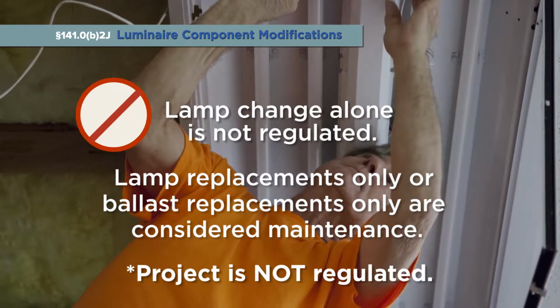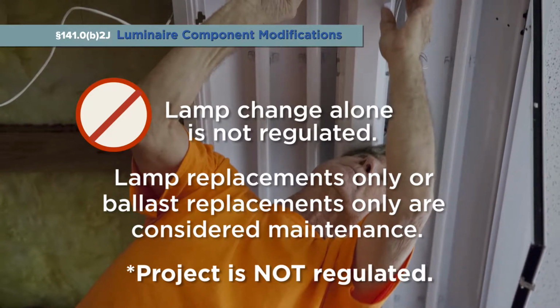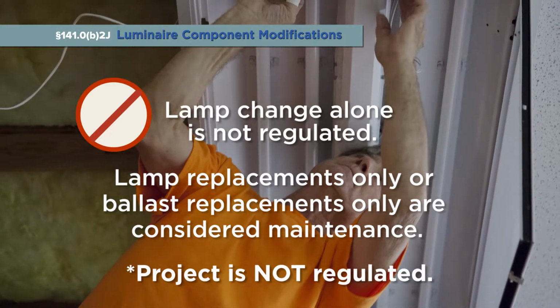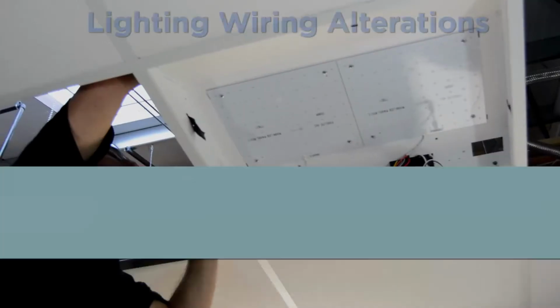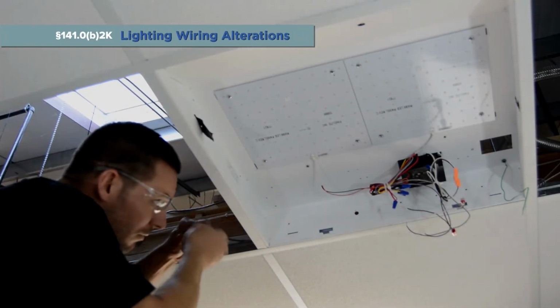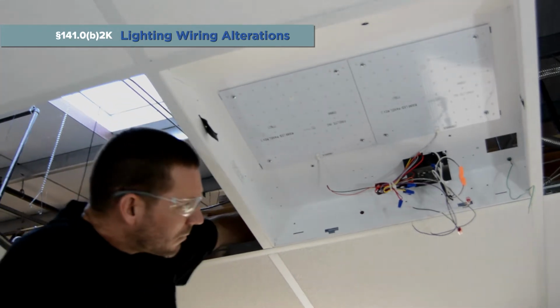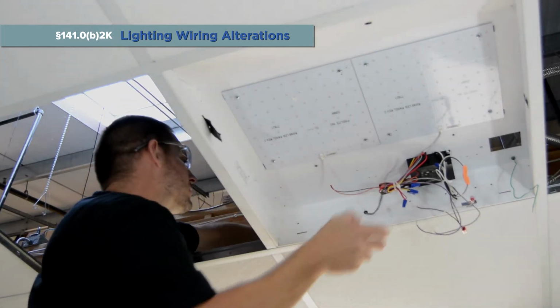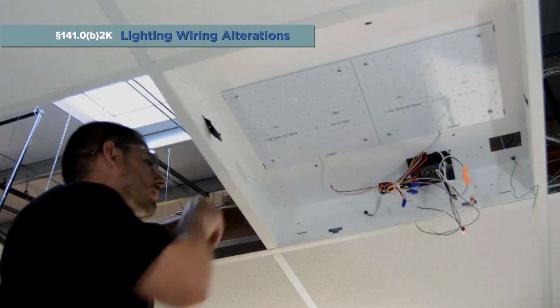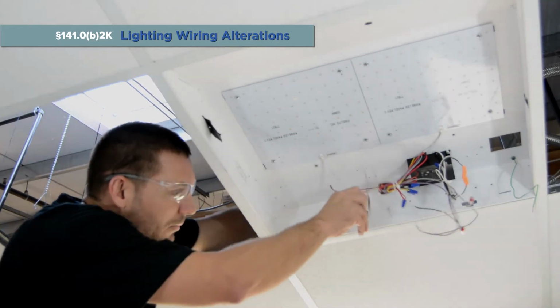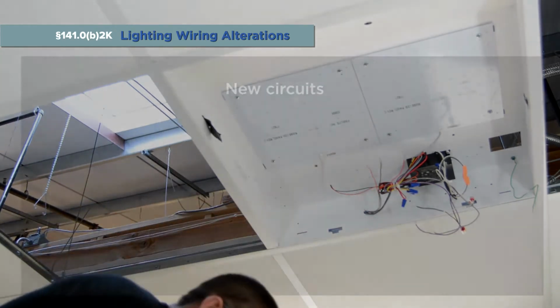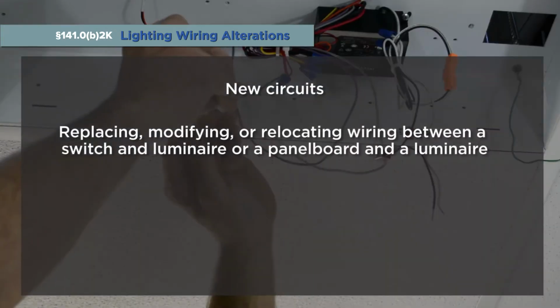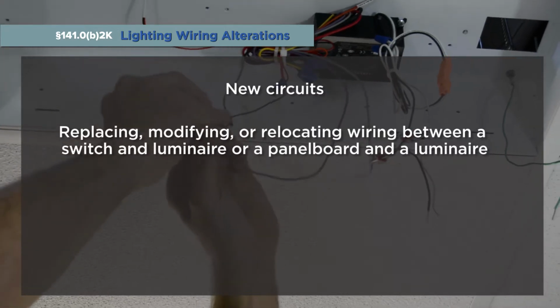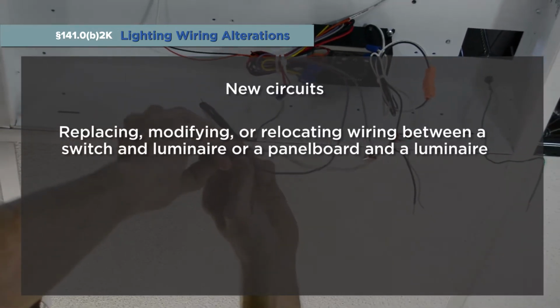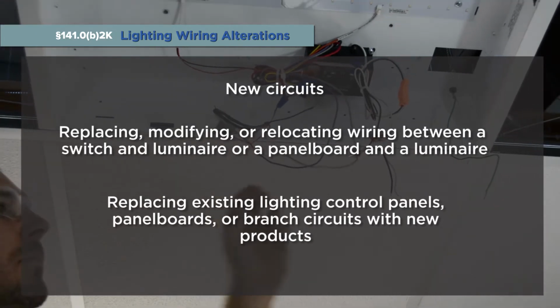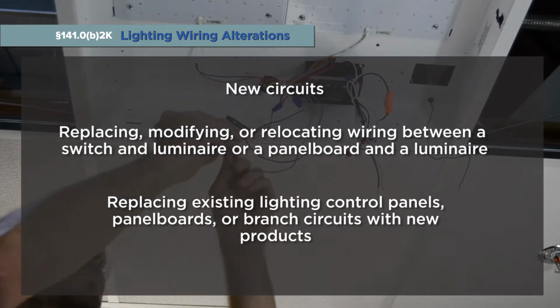Lamp changes alone, or even ballast or driver changes alone, are considered maintenance and are not regulated under the Energy Standards. This brings us to the last type of project for indoor lighting alterations: lighting wiring alterations. These alterations are listed under Section 141.0B2K. The scope of work under lighting wiring alterations includes adding new lighting circuits, replacing, modifying, or relocating wiring between a switch and luminaire or a panel board and a luminaire, and replacing existing lighting control panels, panel boards, or branch circuits with new products.